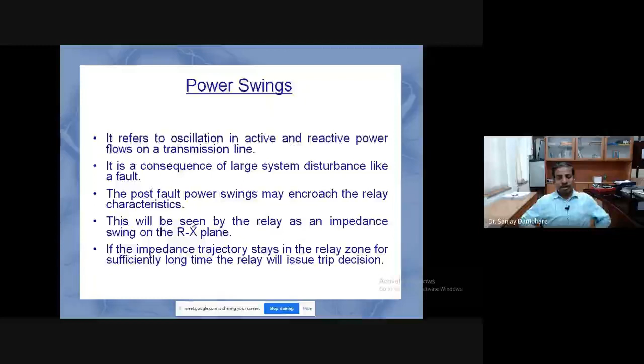This is the transmission line characteristic, and these are coming from the generators. This is the generator at the sending end, this is the generator at the receiving end, and then this is one voltage, another voltage, and this is the relay characteristic. Okay, so this operating point during the power swing may travel towards the relay characteristic, and if it stays for sufficient time, then the relay may trip. Now, there is a peculiar phenomenon that when this operating point comes like this and hits this particular line, at this particular point the voltage is zero, right?